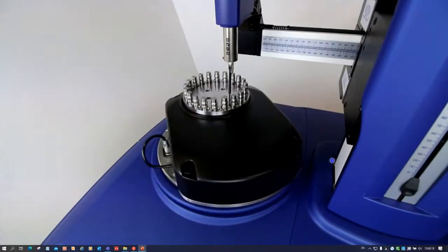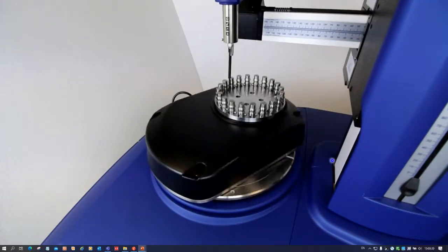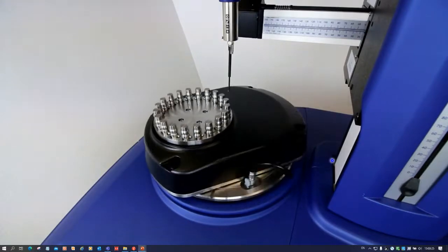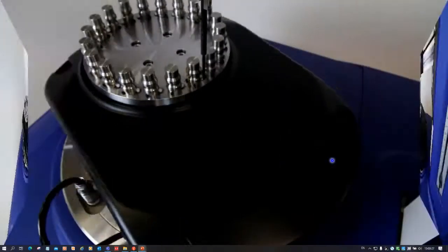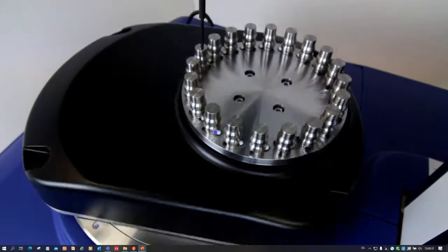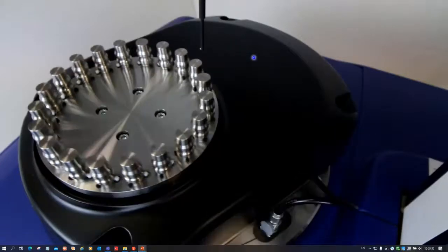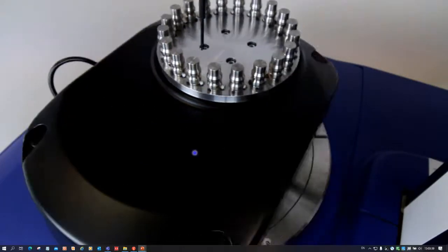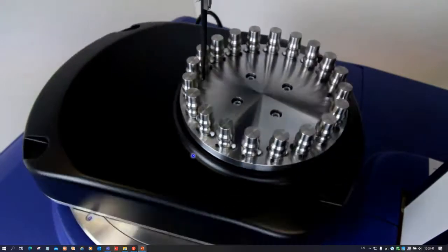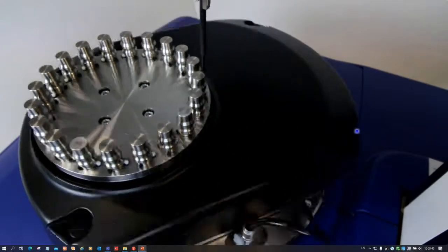So we're measuring the first sample there and then moving off, and you can see we're going to move to a different location. We've indexed round to the next part. One thing to note here is that the weight of this is offset but it is counterbalanced. There is a counterbalance inside here to make sure that the weight is balanced evenly about the spindle axis. So when we're measuring on the carousel there is no loss of accuracy, and we'll have a look at some of those results in a minute.